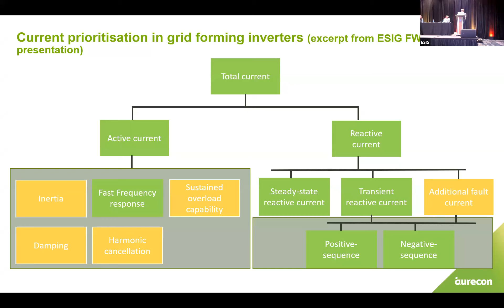Now I'm changing the color coding. I should admit I've made one change - the boxes we had in the previous slide subtly changed. In the previous slide I called everything damping. Now this year I've classified that into electrical damping and electromechanical damping, because the control system and control loops, and their placement within the cascaded control system of a grid forming inverter, are coming from very different parts, if you want to provide electrical or electromechanical damping. Nothing else changed.